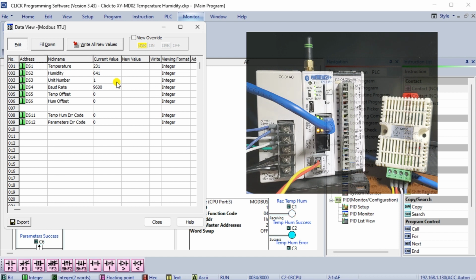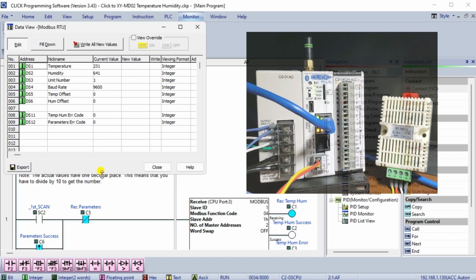The unit address is DS3, the default is 1. DS4 contains your baud rate, which is the default 9600. DS5 is the temperature offset for calibration. As you put this number negative or positive, you can actually calibrate the temperature that you're reading in. DS6 is the humidity offset for calibration. Again, you can go plus and minus on that humidity, so if you want to calibrate it, you can do that with this value.